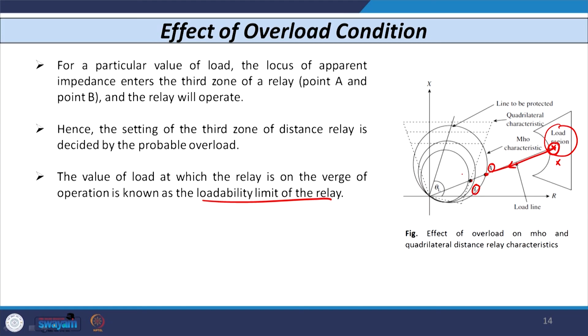If I use the quadrilateral relay, then it has a better loadability limit because the point comes after this point A, and it can accommodate more value of fault resistance. So, the quadrilateral characteristic is better as far as power swing is concerned, as far as the overloading condition is concerned, or as far as the incorporation of fault resistance is concerned.